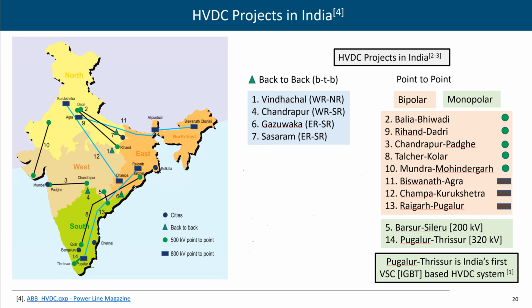Suppose in bipolar one line is lost, then the ground acts as the negative, yes. And now if the negative conductor goes bad, then ground will act as positive—it acts as the opposite return path. But then it is not gelling up, because the ground will always carry less current. Ground means it is simply acting as a return path.